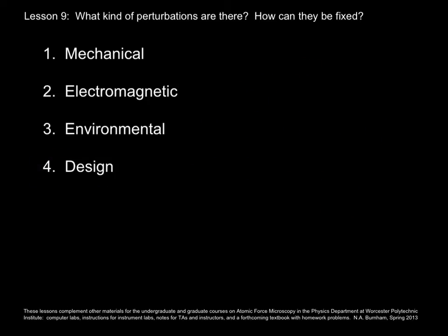In summary, then, there are three types of perturbations about which you can make some modifications and maybe help your imaging. And about 3 times a year, I schedule some time to go down into my lab and check for all these types of perturbations, tighten loose parts to ward off mechanical vibrations, check that everything is grounded, make sure my air filters are clean, etc., etc.